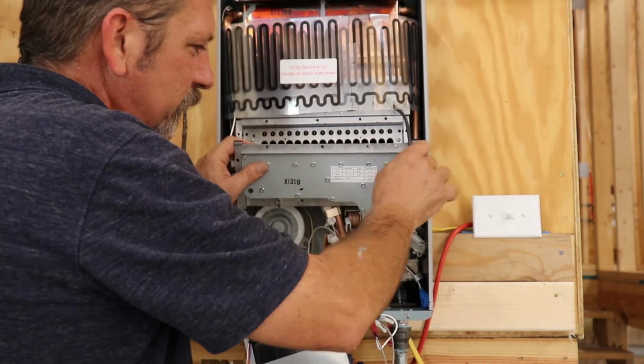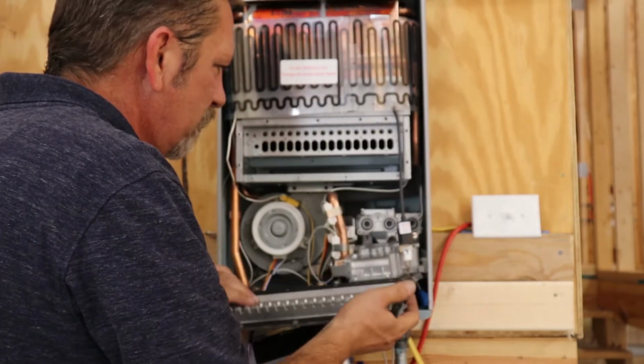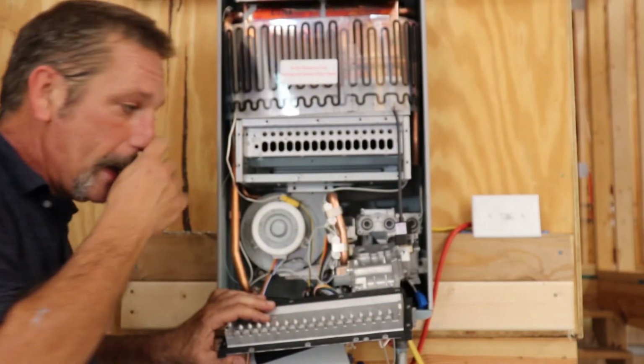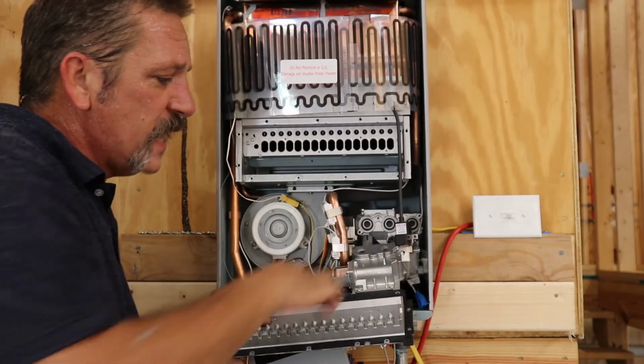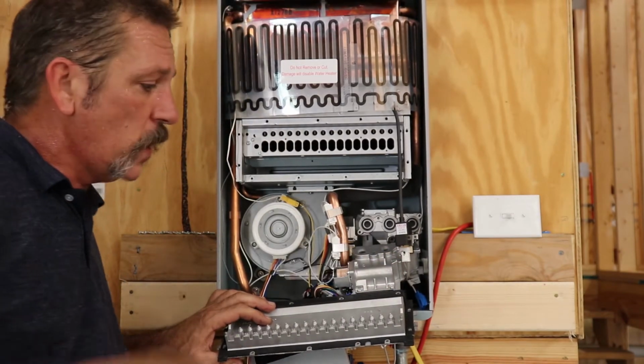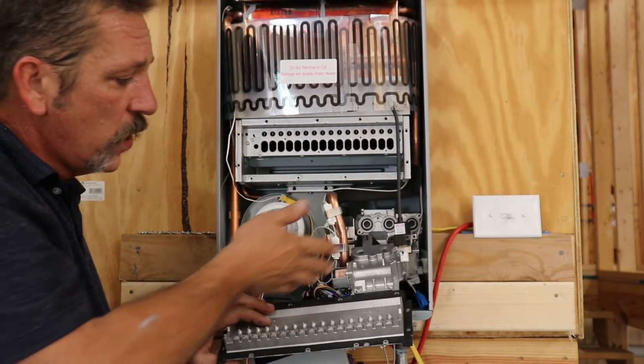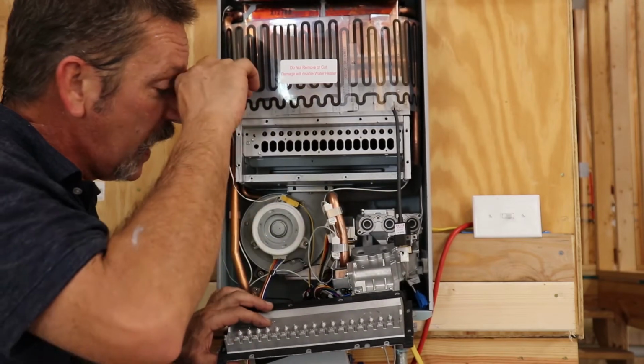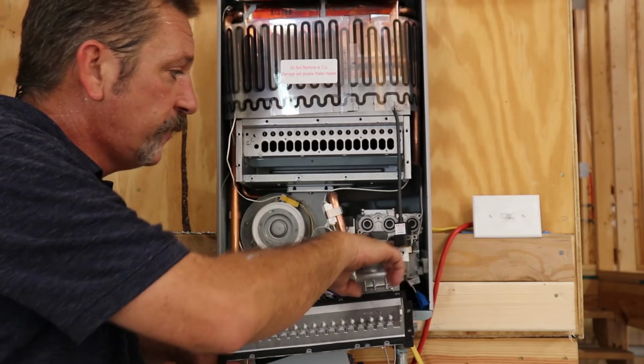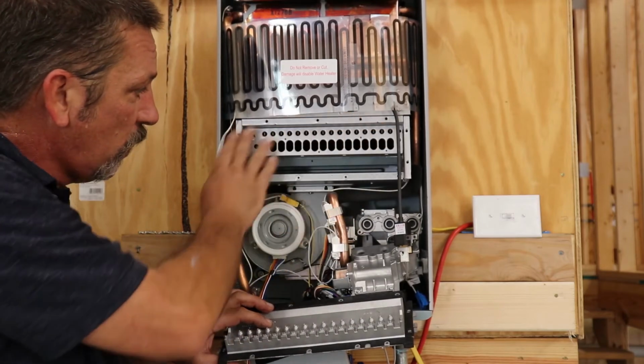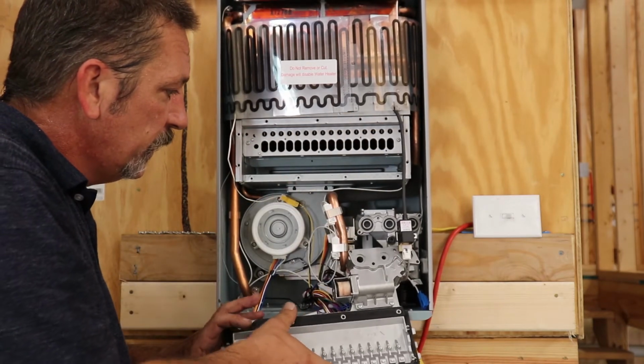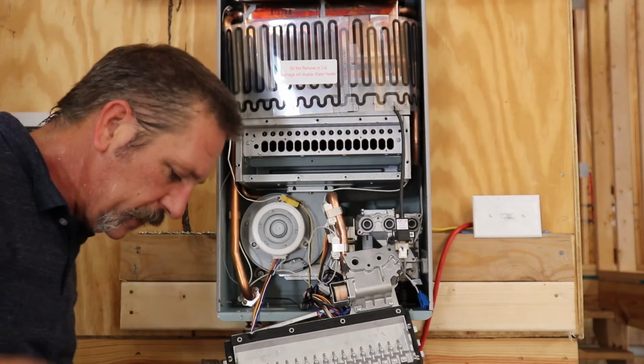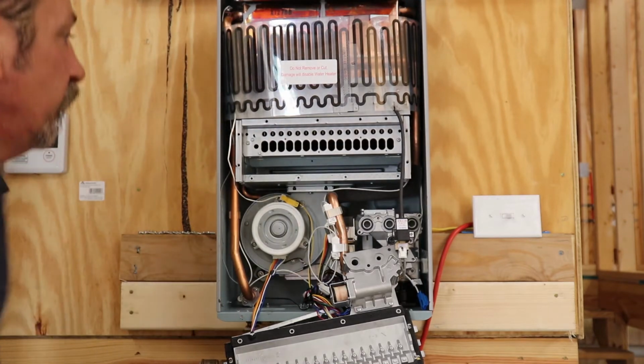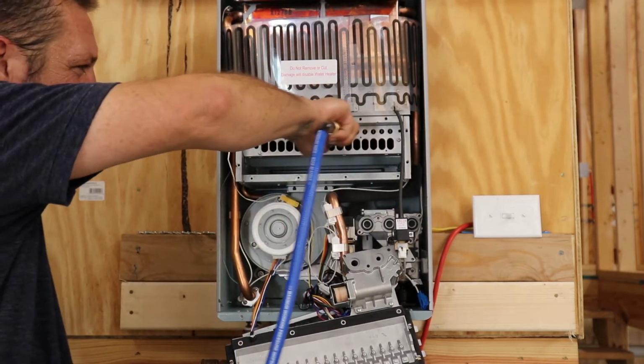All right, let's get these wires out of the way so you can see what's going on. It's actually got 2 screws on the back side that was holding that front panel together, so there's about 6 screws there that I took out that I didn't have to. Pretty much the 4 on the gas valve down here and then all these around the top. But here's your burner box, and what you're gonna do is blow this out.